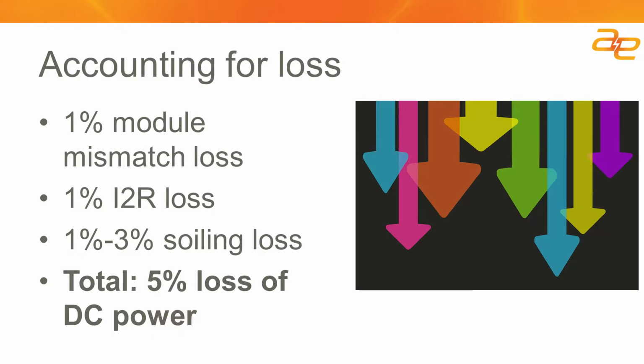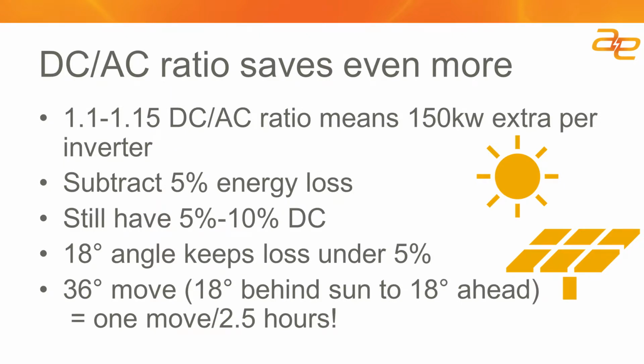So trying to keep 0.1% module output from the modules is probably overthinking, over collecting, or overworking the system. So with a typical tracker site design, you've got a DC-AC ratio of somewhere between 1.1 and 1.15. Those are pretty typical. So that translates to a 1 megawatt inverter having an extra 150 kilowatts of excess DC power. And when you take out 5% loss for the components we talked about on the last slide, we still have 5 to 10% of DC excess capacity.